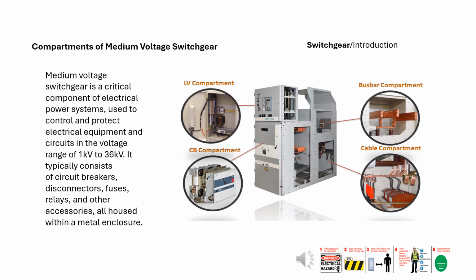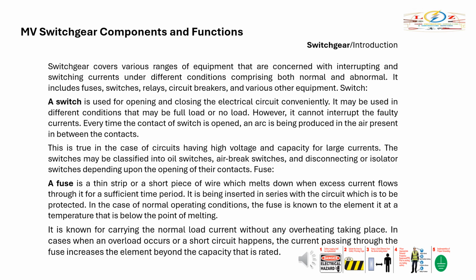The medium voltage switchgear is a critical component of electrical power systems, used to control and protect electrical equipment and circuits in the voltage range of 1 kV to 36 kV. It typically consists of circuit breakers, disconnectors, fuses, relays, and other accessories, all housed within a metal enclosure. Switchgear covers various ranges of equipment that are concerned with interrupting and switching currents under different conditions, comprising both normal and abnormal. It includes fuses, switches, relays, circuit breakers, and various other equipment.